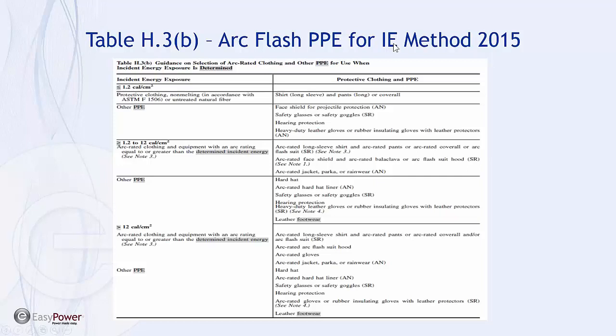And what do we do when we calculate incident energy? Well, we were allowed before to cross-connect, cross-pollinate incident energy calculation and the lookup table. Now, we can't, and I'll show you where it specifies that in NFPA 70E. What this table allows us to do now is once we've calculated incident energy and we know specifically what it is, if we're below 1.2, then again we suit to 1.2.